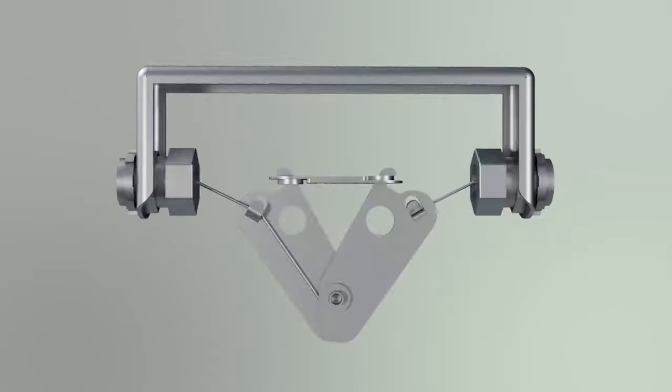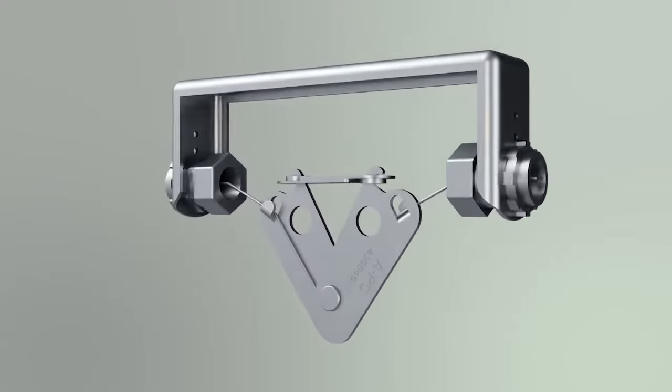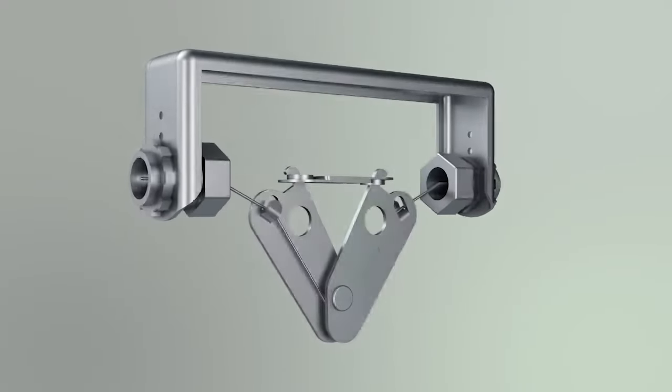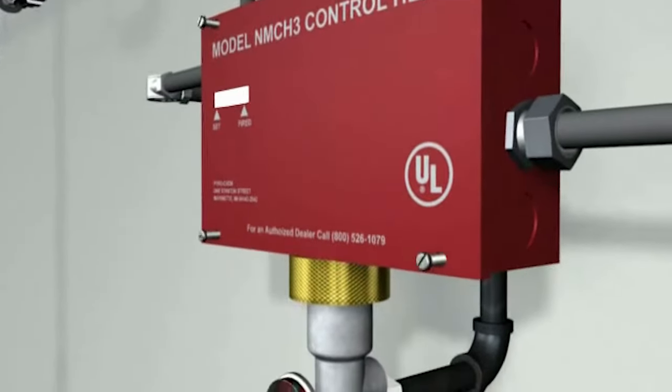In the event of a fire, when the temperature rating of the fusible link is reached, it separates, releasing tension on the wire connected to the mechanical control head located remotely or on the pressurized agent tank.